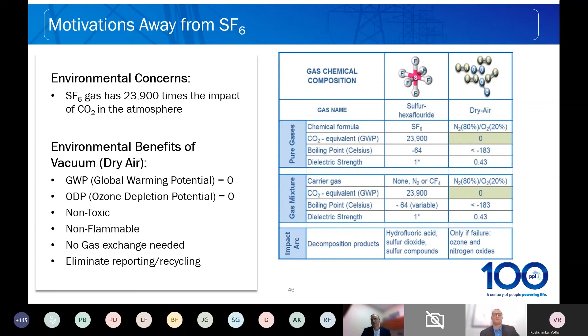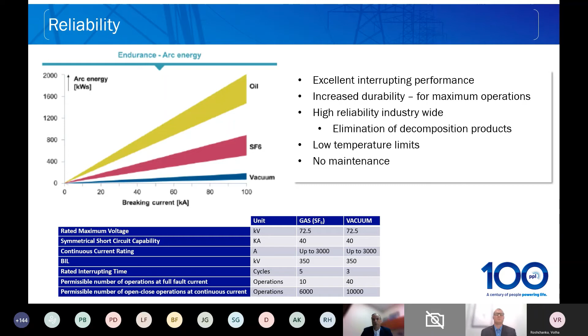As mentioned earlier, SF6's components impact CO2 in the atmosphere, and there are other environmental benefits to alternatives being non-toxic and non-flammable, eliminating reporting, recycling, and handling issues. But besides environmental impacts, there's also reliability. As Brian and Neil mentioned, vacuum technology provides other benefits: a higher number of maximum operations before interrupter replacement, faster interrupting time, and performance at rated nominal or short circuit current for longer durations through the breaker's life cycle. Long term, this leads to less maintenance and longer use, which is good for customers and good for PPL as we minimize maintenance long term.